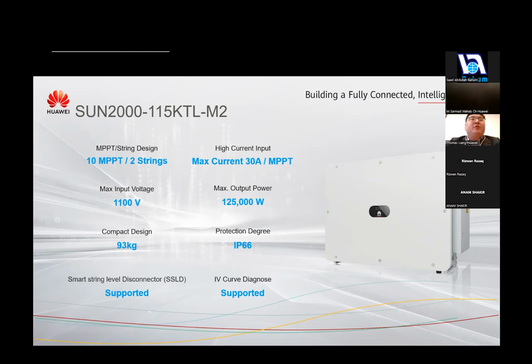And it also supports module-level disconnector. It will also support IV curve diagnosis to help clients detect the performance of the PV modules. And as per the third-party certificate, it can detect 14 types of PV module faults.